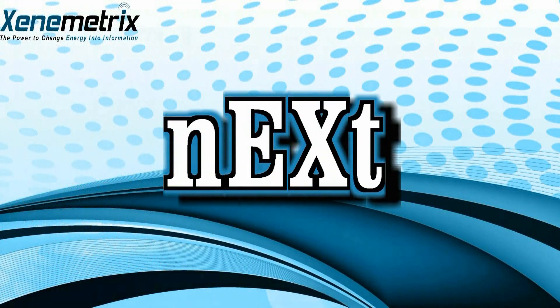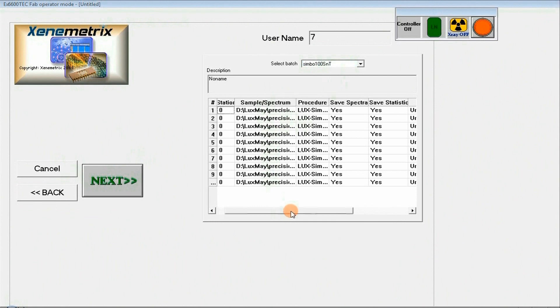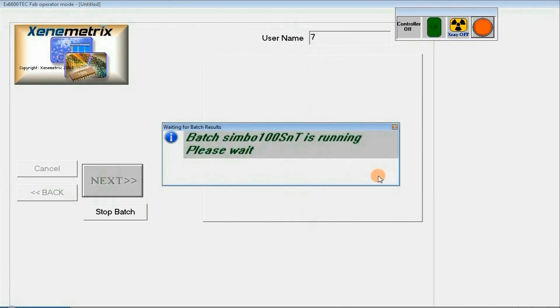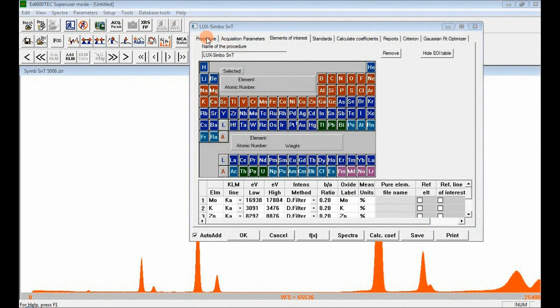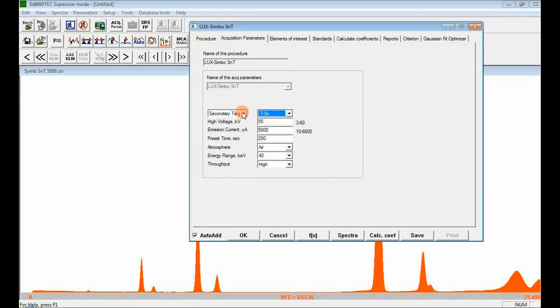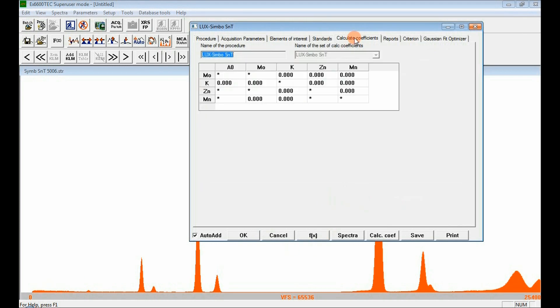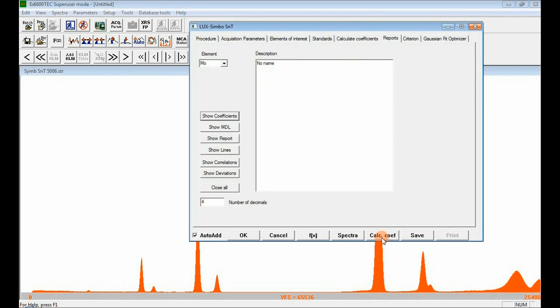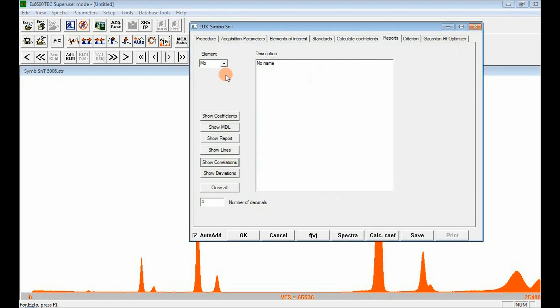Next is an analytical software package with powerful abilities, a user-friendly intuitive interface, and great analytical performance. Next enables building quantitative analysis procedures using the built-in wizard with automatic peaks assignment during the acquisition of a sample. An operator can promptly create their own calibration curves for any analytical requirement with six different regression methods and selectable intensity extraction.